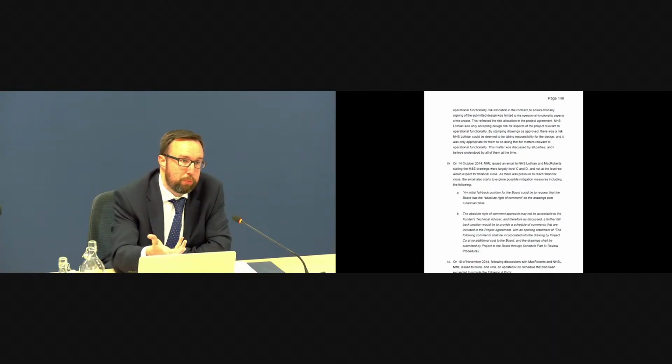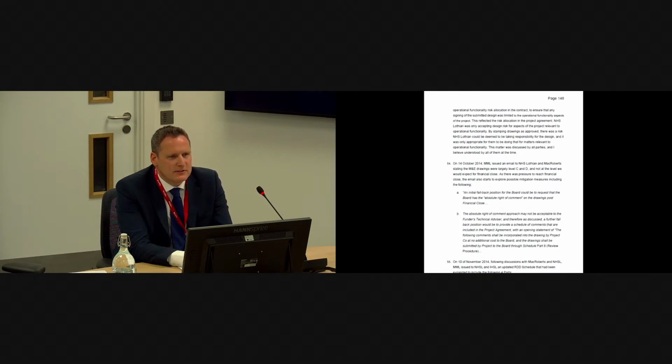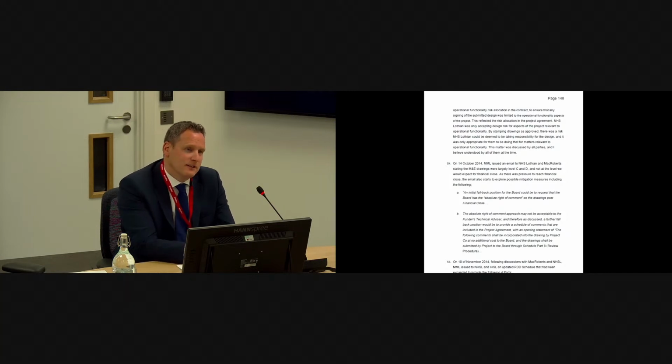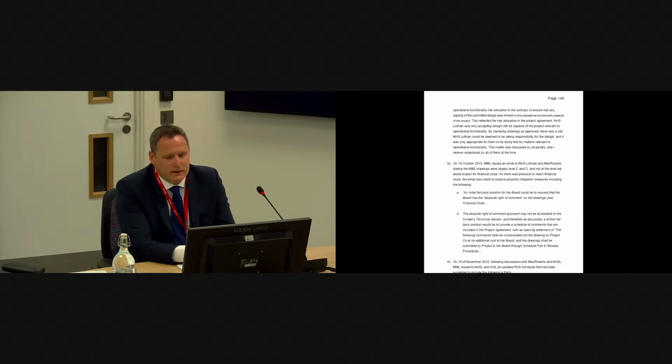Why couldn't you just produce your room data sheet and take it as read that it would have all the right environmental parameters? Yeah, it's interesting because there's a clause 2.60 in the SHTM, so it's in SHTM 0301, which directs you to the ADB sheets for the specific characteristics for the room. There's a slight contradiction in that. The SHTM is telling you to go to the ADB sheets for your ventilation requirements, but there's now a known issue. I'm not sure if that was known at the time, that there were anomalies with the data in the ADB sheets, but it's something certainly we're well aware of now.